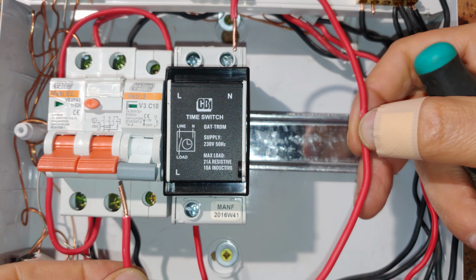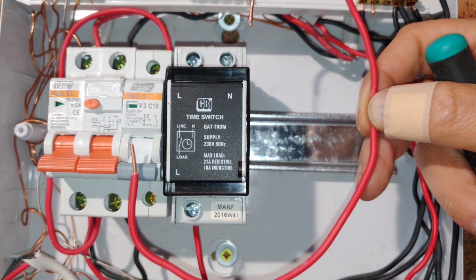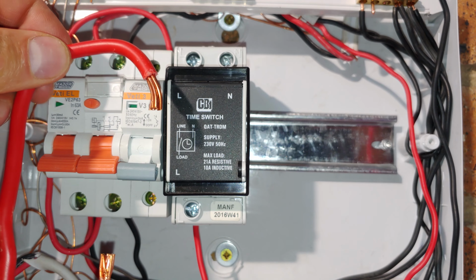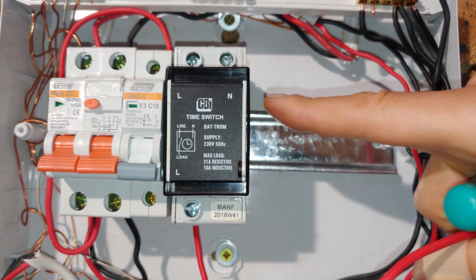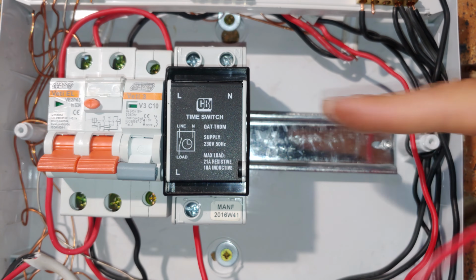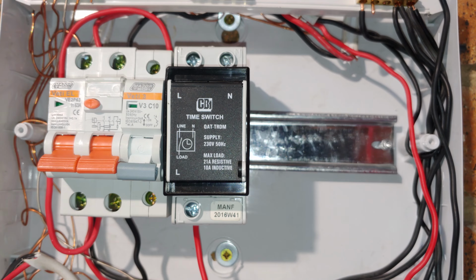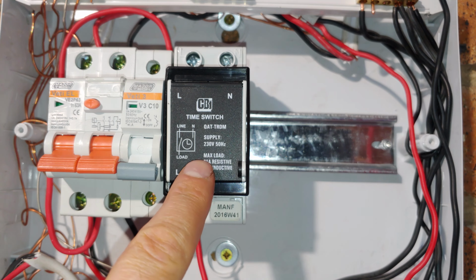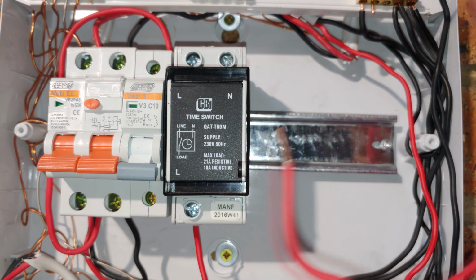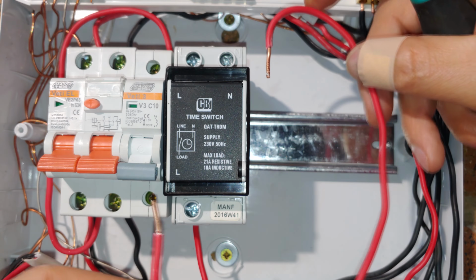Now, if you are going to install a 30 amp circuit breaker, then you will need to use a much thicker wire, and you'll also need to look at a stronger timer. So you need to match the timer to the application. Now, because this is a pool pump and the current is less than 10 amps, keeping in mind it is a motor, so it's inductive, I can use this 2.5 millimeter cable.